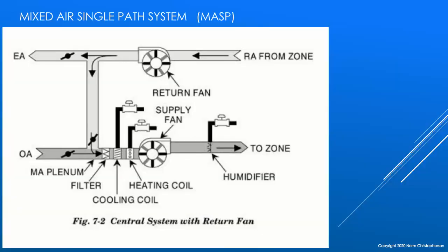The mixed air single path system is far more common. In the 100% outdoor air unit, we were bringing all air in from outside, treating it, and then exhausting it. In this system, we bring maybe 10 or 15% of our air in from the outdoor air side, but we take most of our air back from the return air side and mix it with that outdoor air — we call that mixed air. Then we run it through the filter, cooling coil, and heating coil as necessary, and the fan moves it down the duct into the zone. When you open the outdoor air damper even 10 or 15%, you are pressurizing the building.